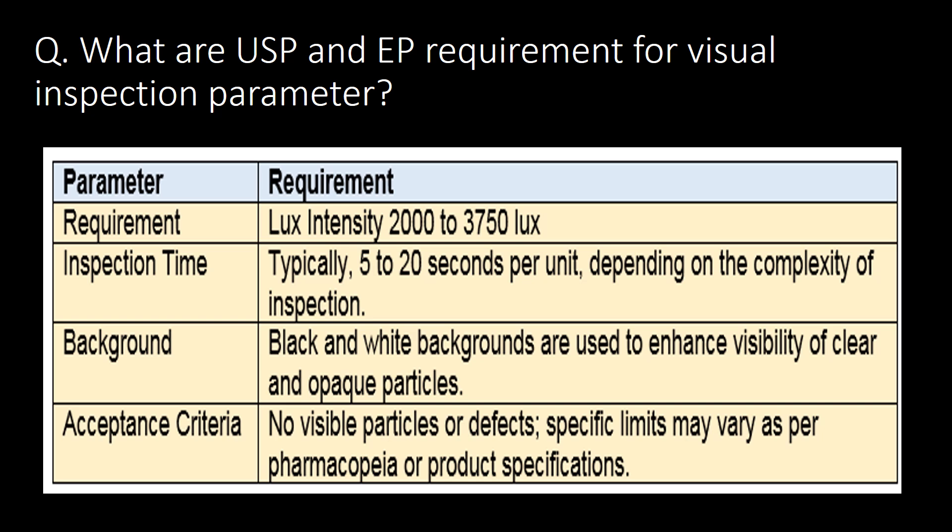What are the USP (United States Pharmacopoeia) and EP (European Pharmacopoeia) requirements for visual inspection parameters? The requirements are mainly for lux intensity of 2000–3750 lux, inspection time typically 5 to 20 seconds per unit, black and white backgrounds to enhance visibility, and acceptance criteria of no visible particles or defects, with specific limits varying per pharmacopoeia or product specifications.